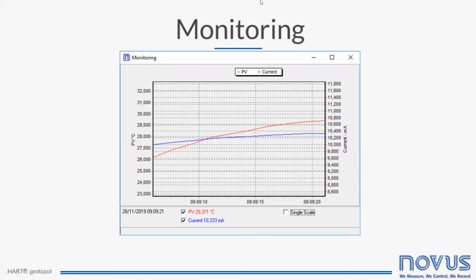What are the highlights you see on HART devices? The first one is field diagnostics without removing the device from the plant. The second one, easy to upgrade 4 to 20 milliamps legacy systems for digital communication. Can be used or replaced on HART system of any brand. Proven robustness attested by FieldComm Group. Digitally monitor without need for active current loop.